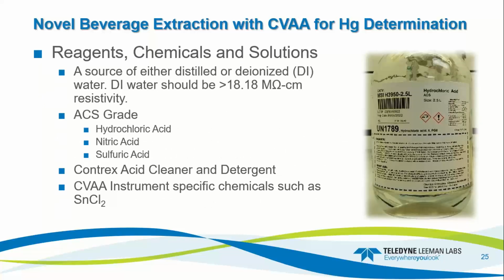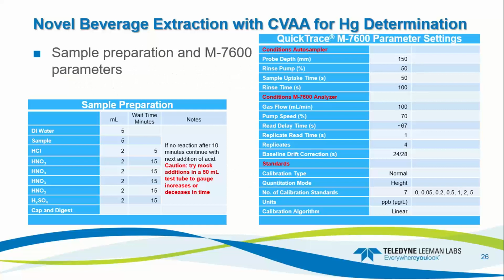The reagents, chemicals, and solutions: you need a source of DI water, ACS grade hydrochloric, nitric, and sulfuric, and then some Contrad acid cleaner. This is what I use in the lab, or similar, and then a cold vapor atomic absorption instrument, and any chemicals specific to that instrument, such as stannous chloride, are going to be needed for this method. So in this case, the sample prep: 5 mils of DI water, 5 mils of sample, 2 mils of hydrochloric. Again, that's that complex or preservation mode.